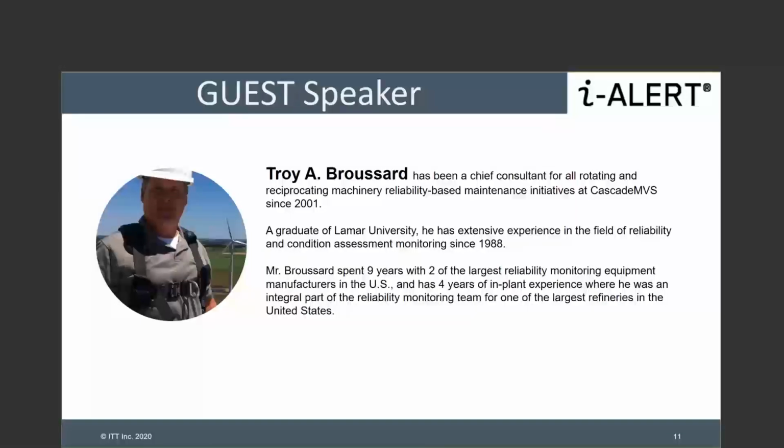So what we see most, to answer your question, Naveen, in unscheduled outages here, especially with the hydrocarbon aspect of it, is seals take out most of the customer's machinery more than any other problem. But that still drives the point of what's causing the seal to fail. Yep. If the seal's properly designed, why is the seal failing? What is that driving force that makes that seal fail?